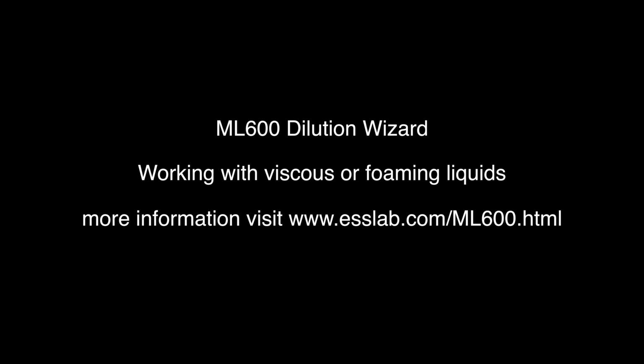You'll note that difference when we're dispensing. Because I don't want so many problems with foaming, we're changing the dispense speeds, particularly of our reagents and the sample. So we're going to change both on the dispense side to the lower rates. Here we're going to change that to 1250 microliters per second as a slightly slower speed, and also change this to the slower speed again.